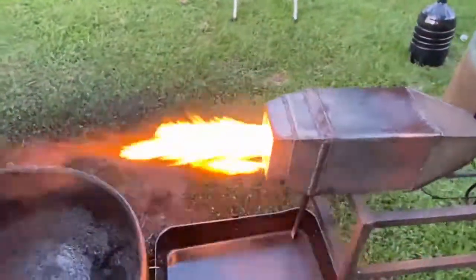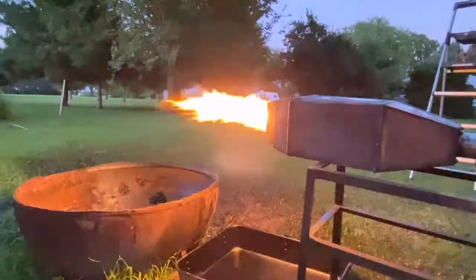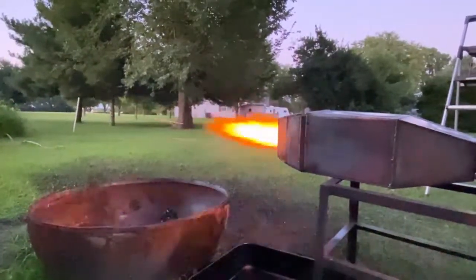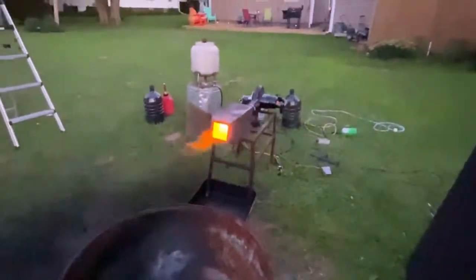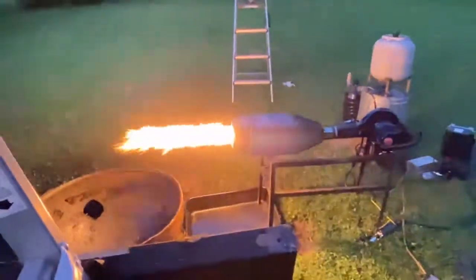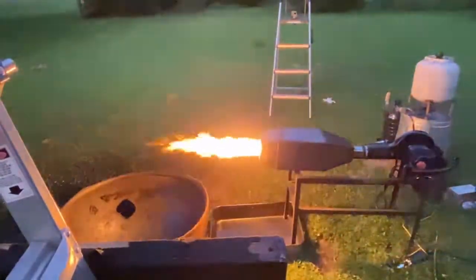So I'm just running this thing through its paces, trying to get it dialed in for you, Rhonda, for some smaller flames. I know you've got a small firebox. This thing would perform a lot better if it had a firebox on the end of it for some of this testing, but for now we're just doing the naked flame testing, seeing how it can do on different settings. I feel like maybe we'd want even a little more pressure on this nozzle — it's kind of finicky on these lower settings. Waste oil is just hard to burn. If we preheated it, it would definitely help out, but it doesn't really need it in most applications, especially if you're firing this into a firebox. It has literally no back pressure right now — it's like a combustion can with no nozzle on it. I should probably give it a shot with a nozzle and see what happens.